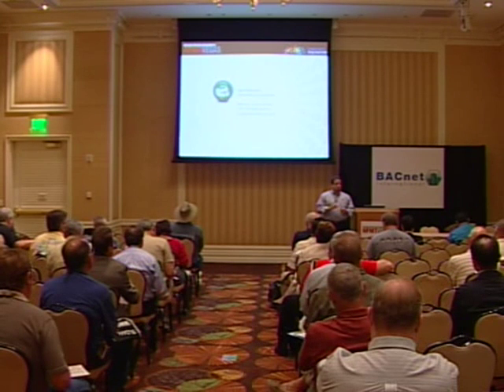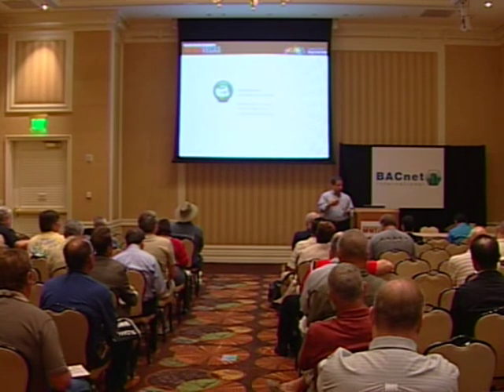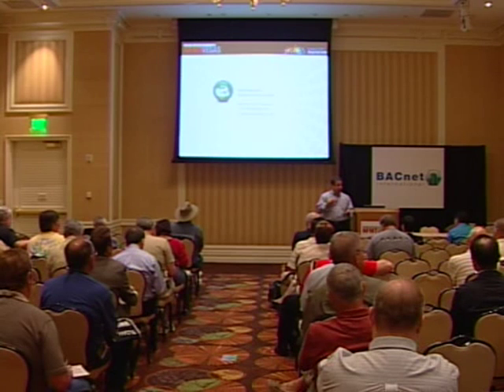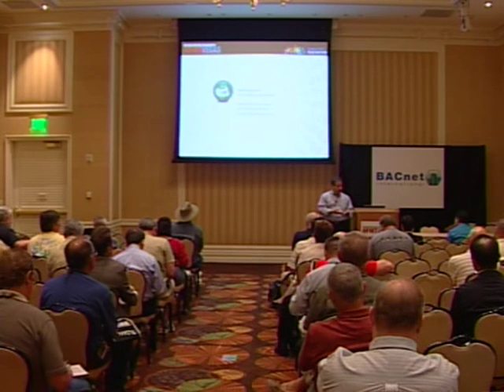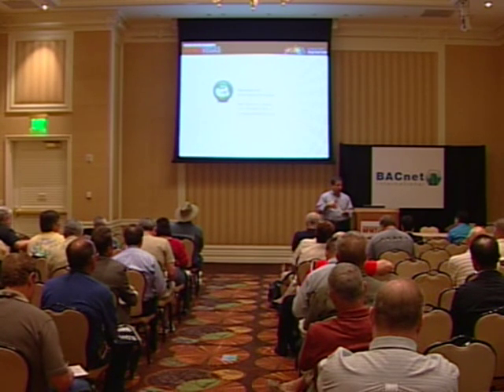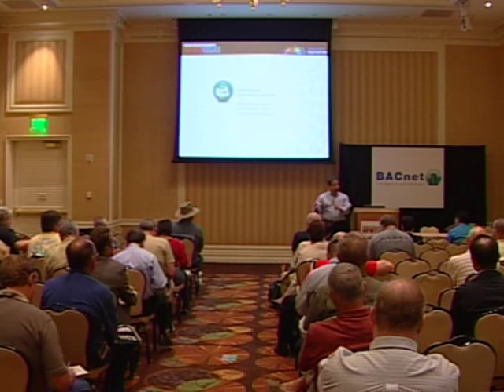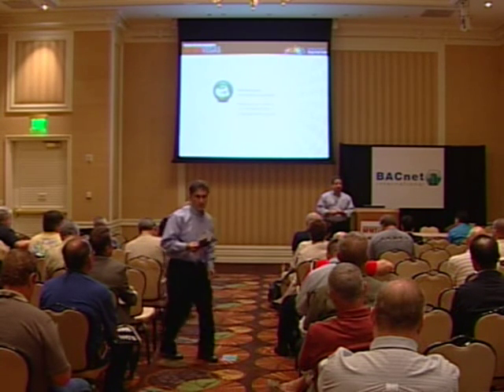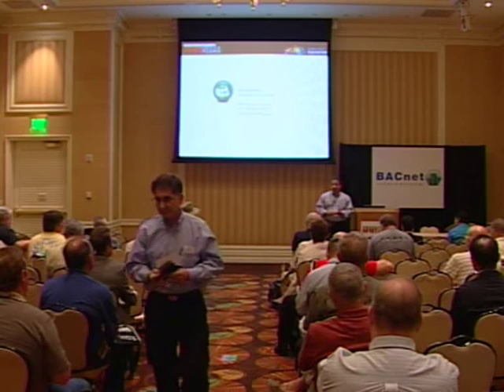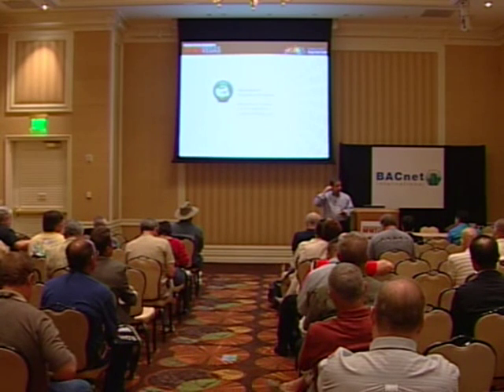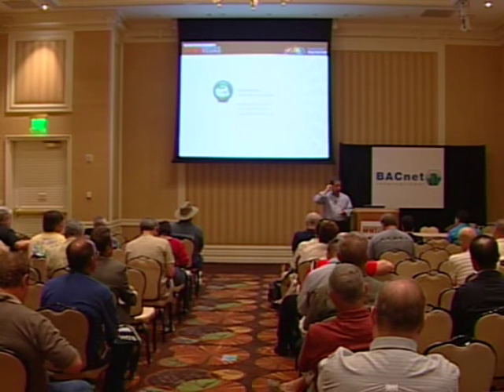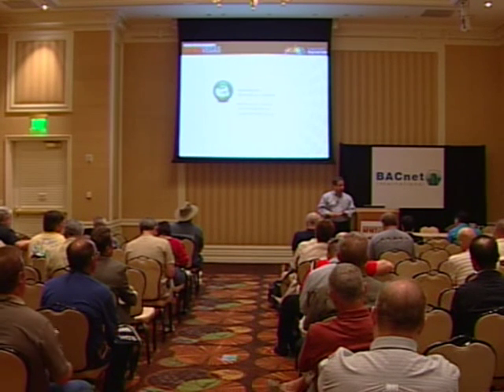I'll give you my personal opinion on DALI. As a manufacturer, we've looked at DALI, and there are two drawbacks I see right now. One is it doesn't have collision detection or collision avoidance in the open protocol standard. And unfortunately, we see too many manufacturers here in the U.S. employing controls on the same network as the ballasts, which can create a lot of conflicts and issues.